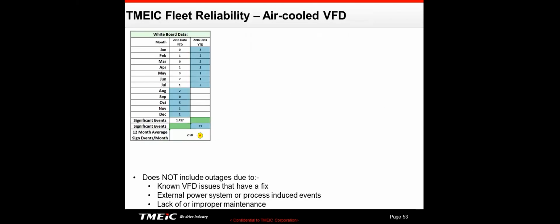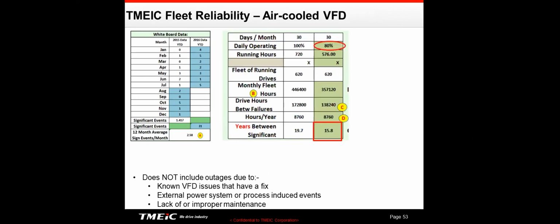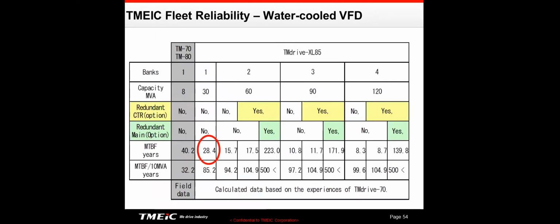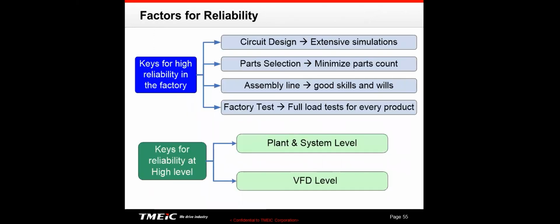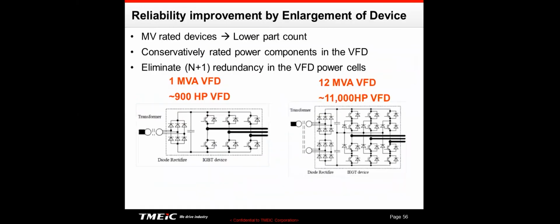So these are some of the reliability statistics from TMEIC. You can see the events, and they track all of these things, and this particular drive has about a 15.8 year mean time between failure. Here's a water-cooled VFD that actually has a 28.4 year mean time between failures. Those are just extremely good numbers. And here's some of the factors that you get into with reliability. You can just glance through there. I'm not going to go through that in detail due to time.